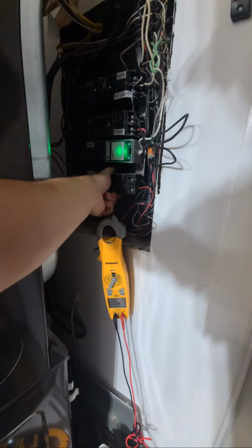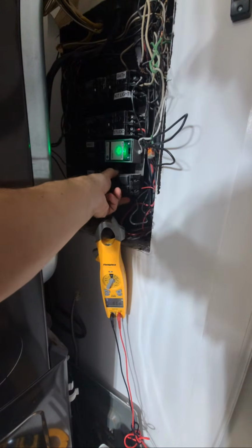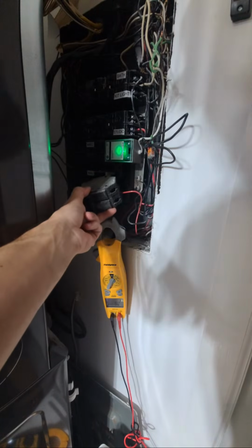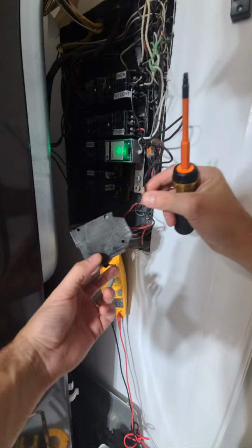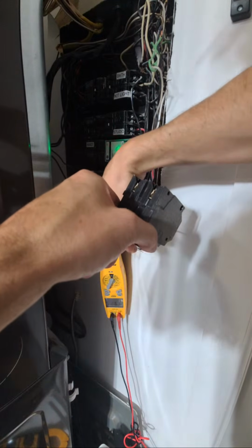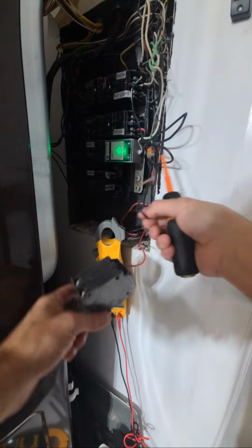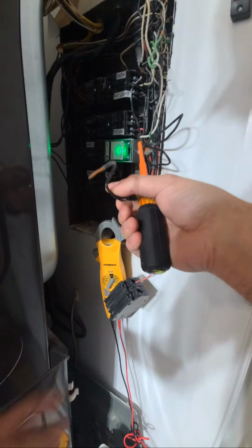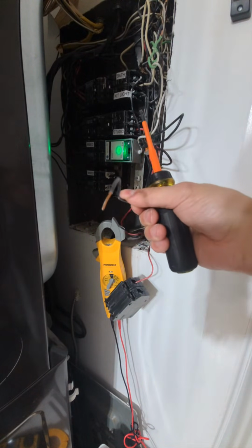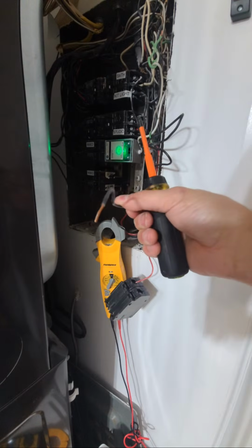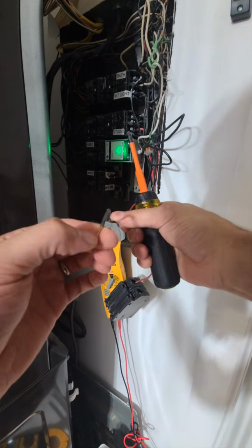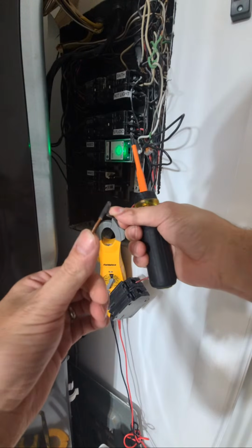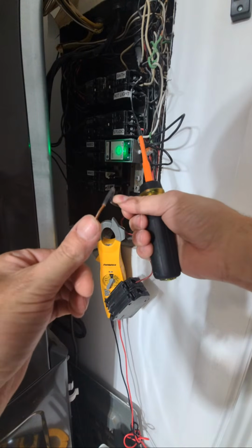All right, so what I was saying, if we pull this breaker, right, and we were to look at the wire, you're going to notice a couple of things, okay? I'm going to show you. When you have arcing, you have pitting of your conductor. You can see where it's got some gray pitting on there. So that's not going to be a good connection anymore. You really need to cut this off and restrip. I'm going to show you why.